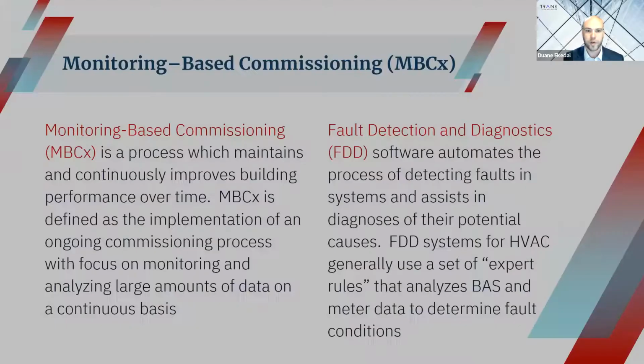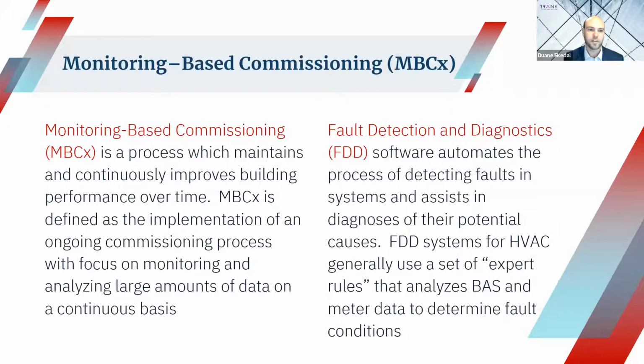A couple of the ways that's happening right now: one is monitoring-based commissioning, and the other is fault detection and diagnostics. Monitoring-based commissioning will automatically perform functional testing on facilities. There are certain analytic tools now that overlay on top of the building automation system, and that will automatically flag anytime the system doesn't operate as designed.